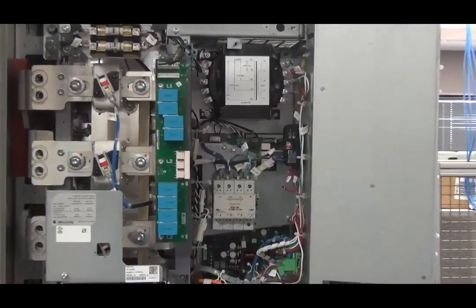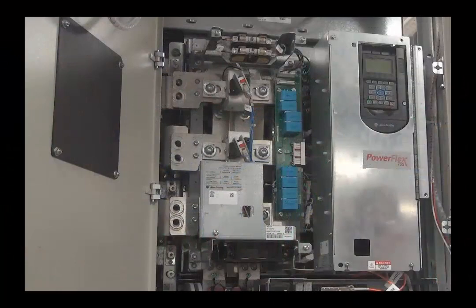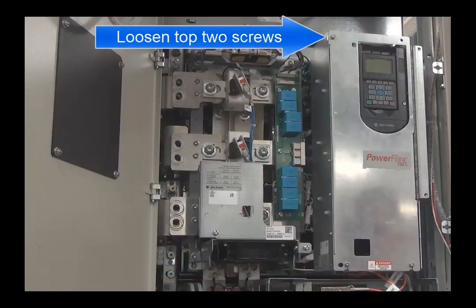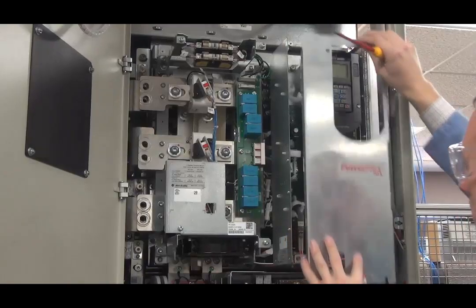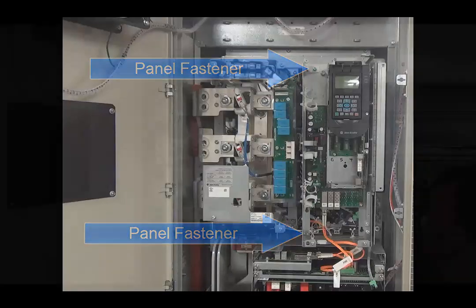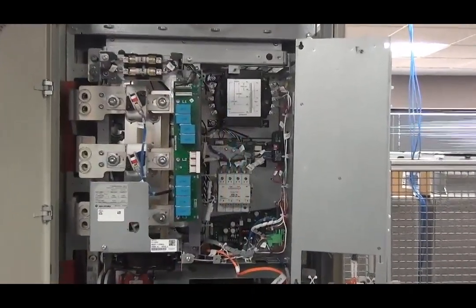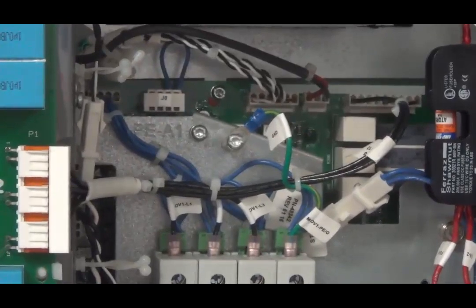To change the PEA1 jumper configuration, a long flathead or T20 screwdriver will be required. To locate the PEA1 jumper, first remove the pod cover by loosening — not removing — the two M4 by 12-millimeter slotted hexilobular screws at the bottom of the cover, and then removing the top two hexilobular screws at the top of the pod. With these screws removed, remove the front cover. Next, loosen the two M4 captive panel fasteners that secure the control pod to the converter control panel, and swing the control pod forward. With the control pod door open, screw the wire onto the drive frame with the right screw to electrically disconnect the jumper, or with the left screw to electrically connect the jumper.